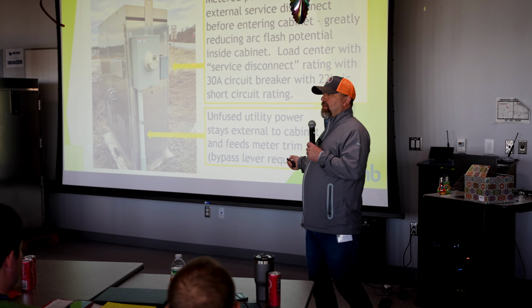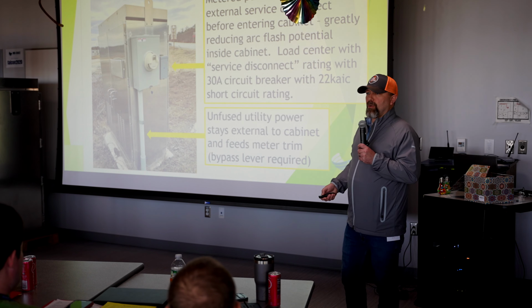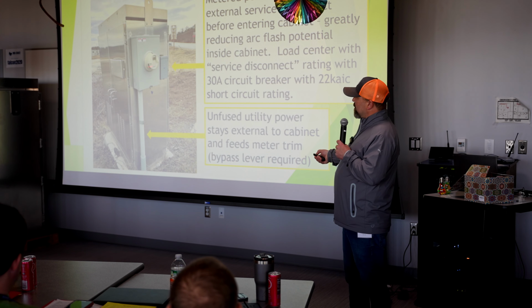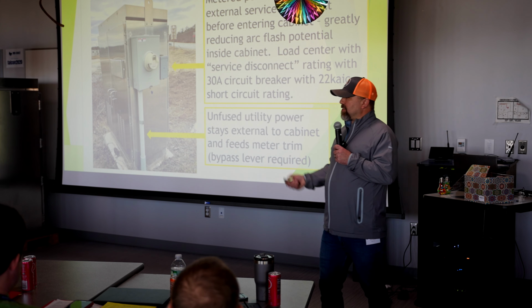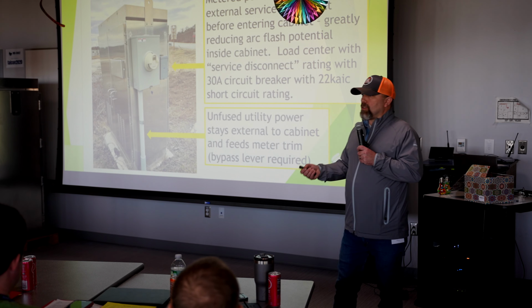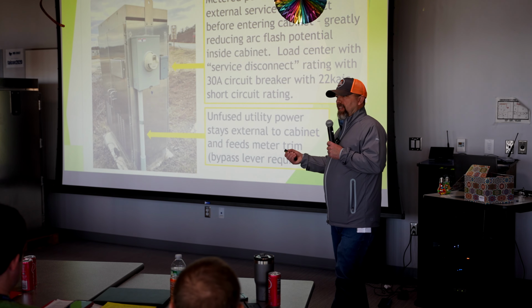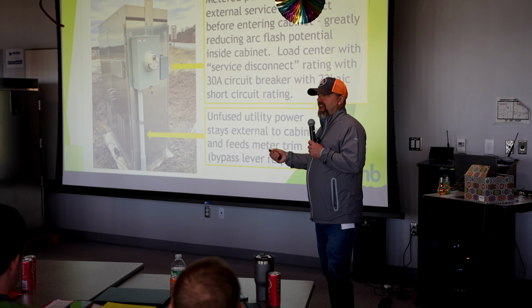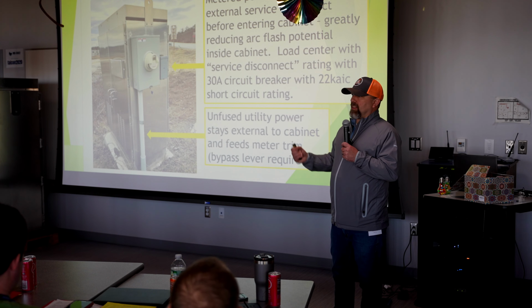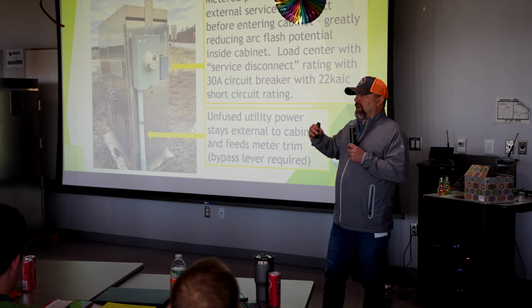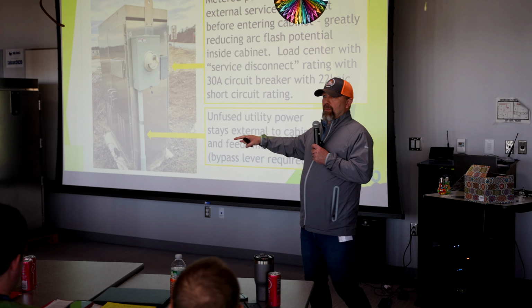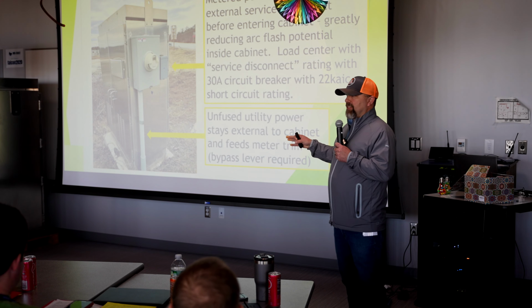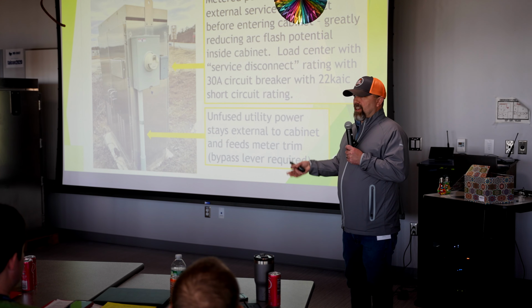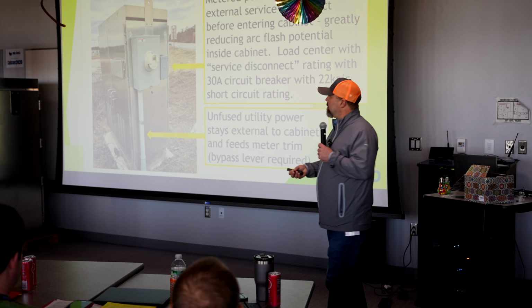Standard practice now, in fact, I think CMP enforces this, is that the meter trims you're using on traffic cabinets have to have a bypass lever. So if CMP or the utility company needs to service that, they can throw the bypass lever, pull the meter, and you don't lose power to the cabinet, because that would be a public safety issue. It's pretty standard for commercial buildings as well.